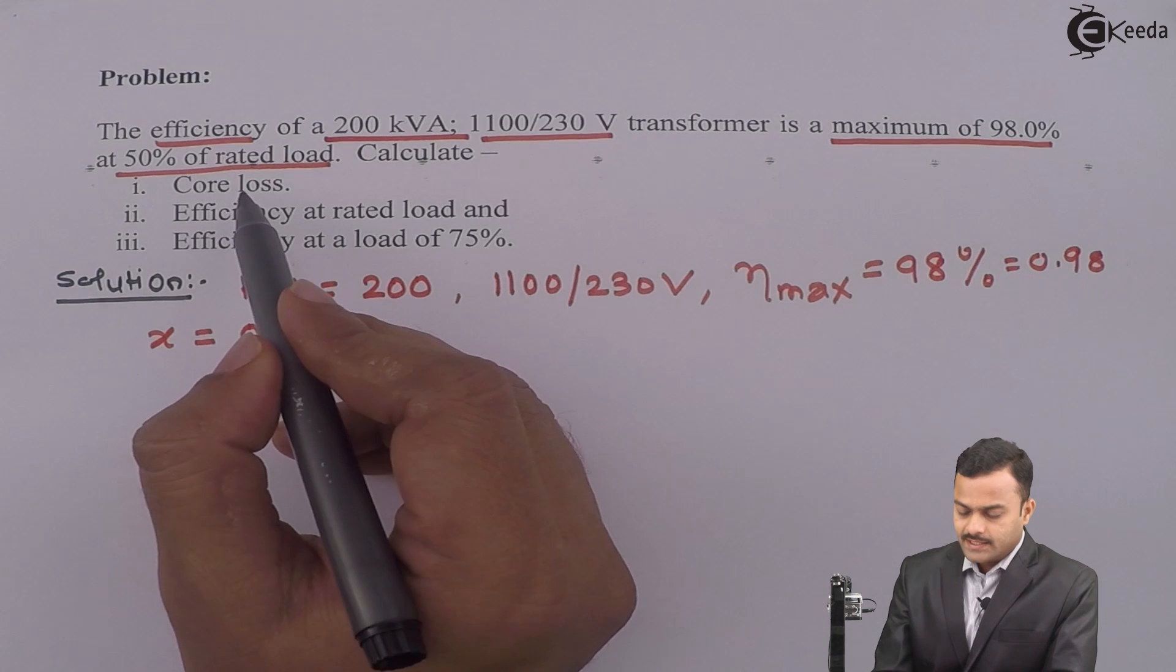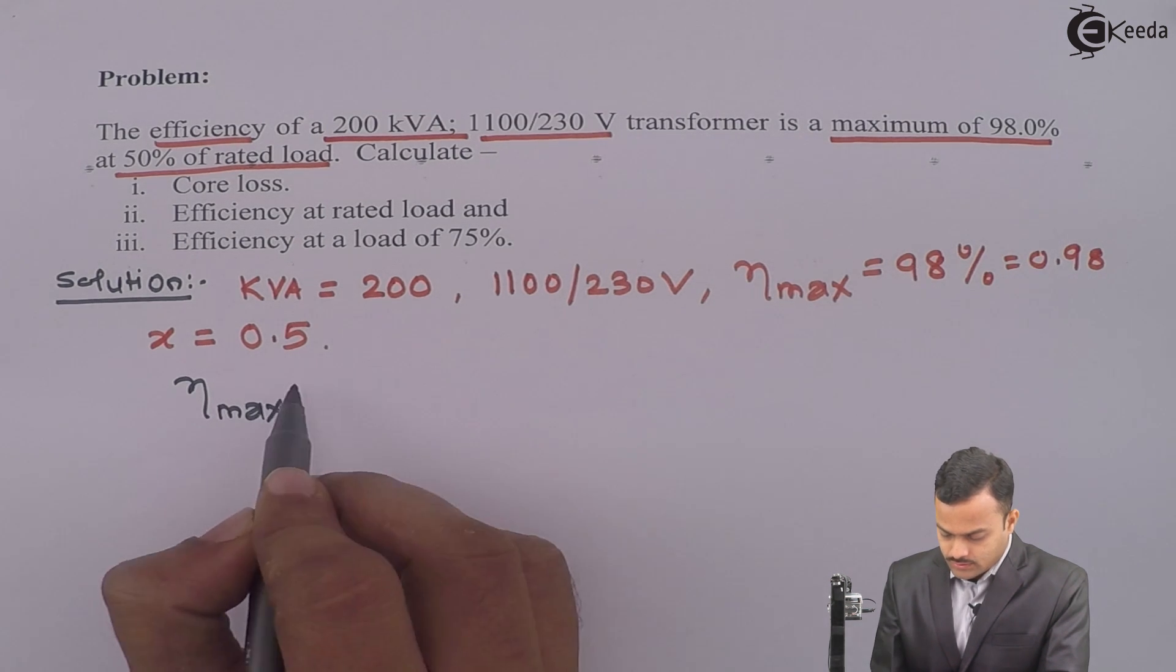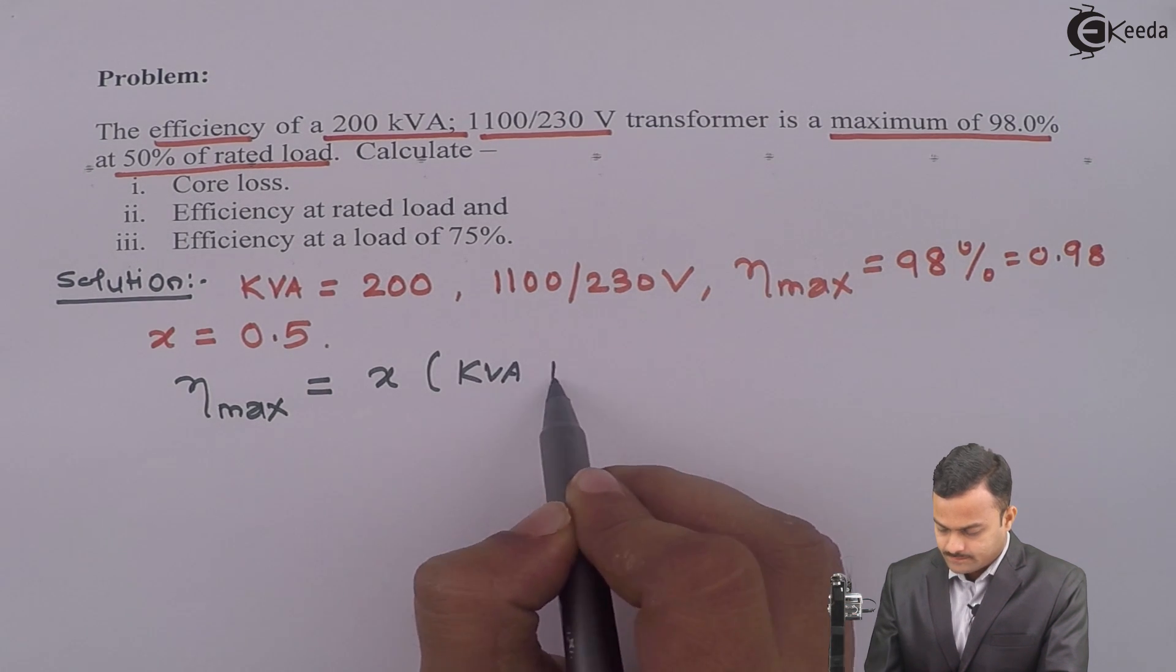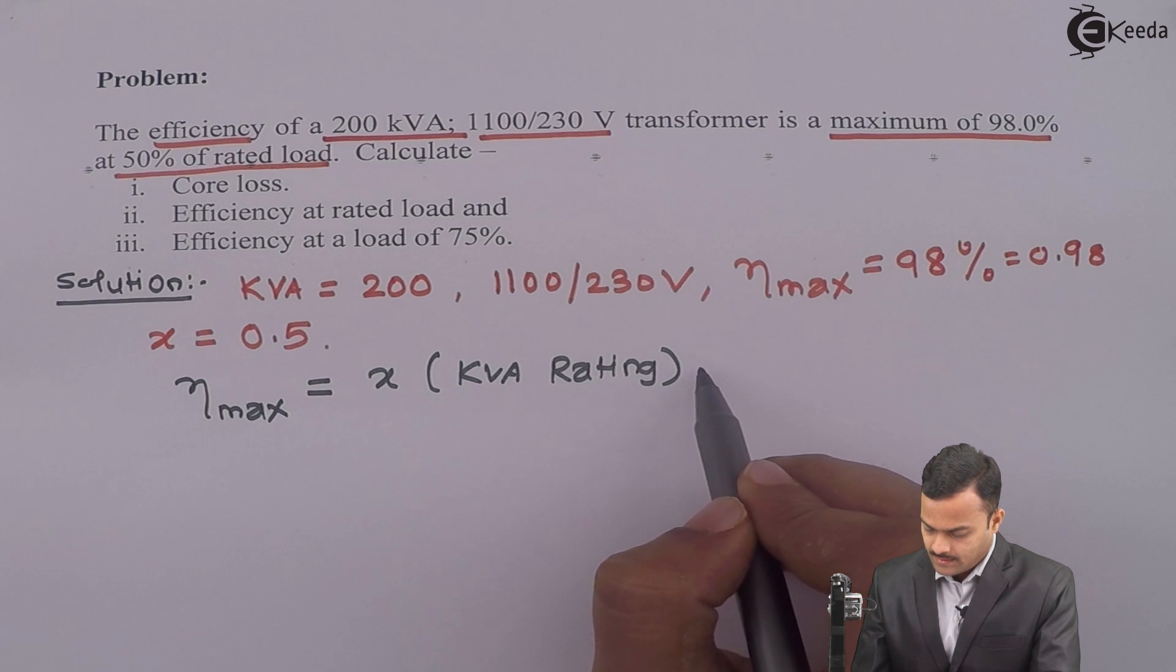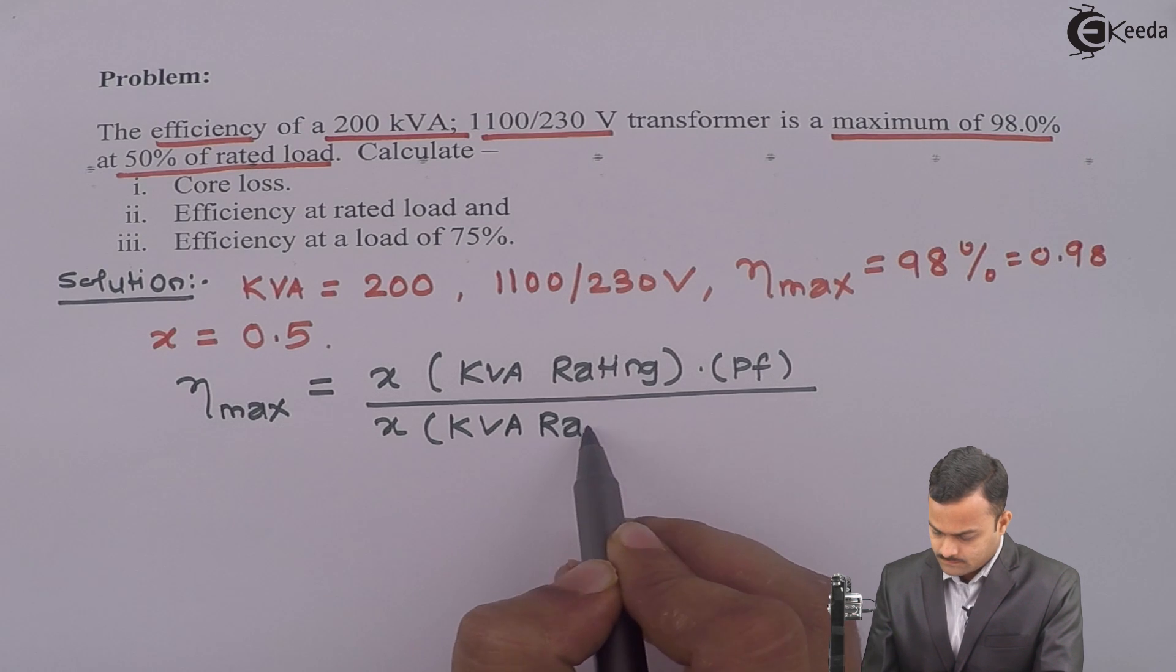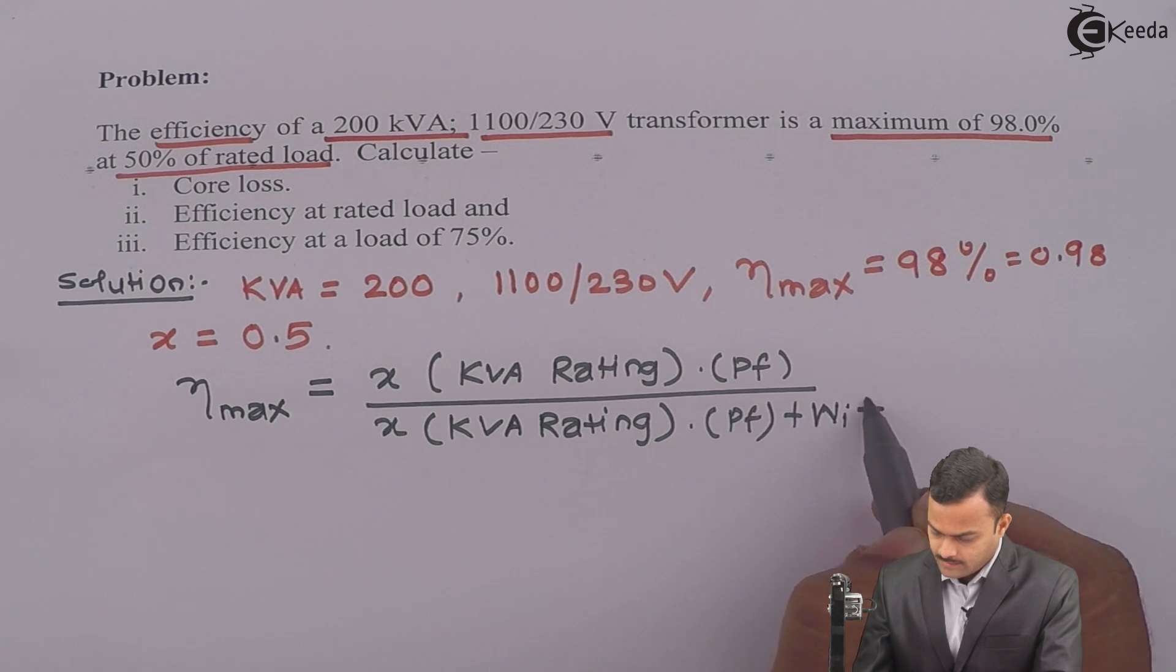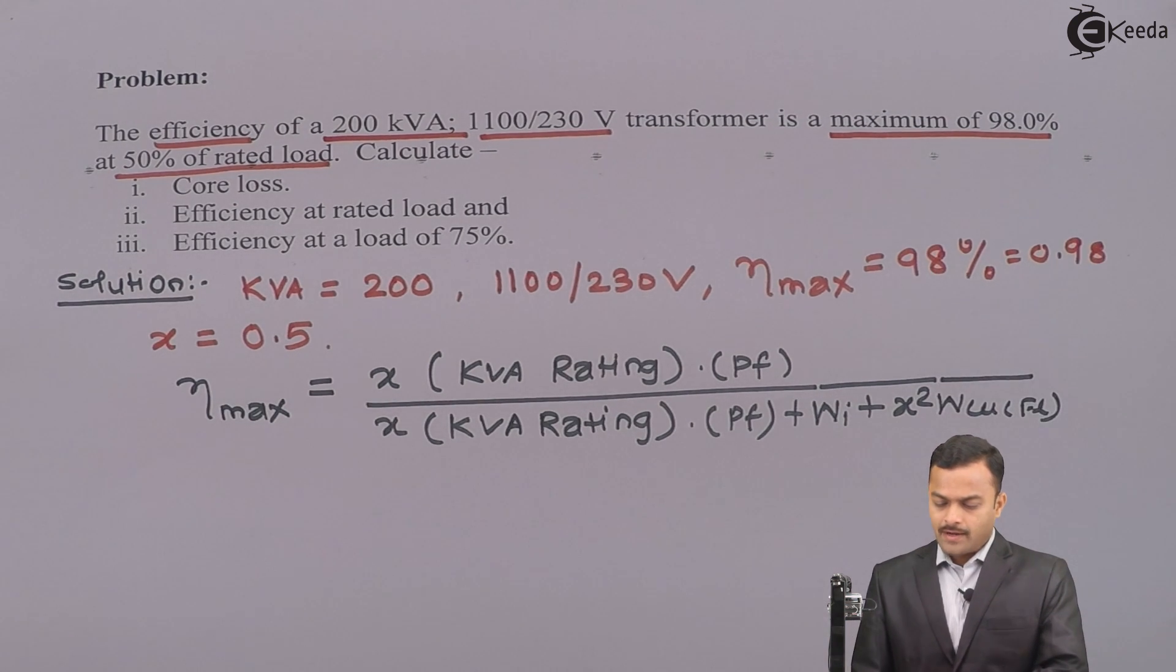Let us calculate the things that they have asked. So first I will write a formula for maximum efficiency. So maximum efficiency is X multiplied by kVA rating multiplied by power factor divided by X multiplied by kVA rating multiplied by power factor plus WI plus X square WCUFL. So here power factor is not given. So let us assume for this problem power factor is unity.